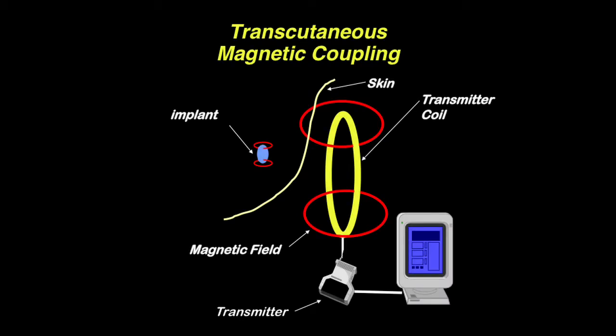We have an outside device that creates a large magnetic field by having a large current pass through it. This magnetic field easily penetrates the tissue, can be coupled to a smaller coil that's inside of the device, and in this way we can transfer energy to the device. Now what's convenient about this is then we can change the transfer of the energy in order to communicate with the device. So we can put a carrier, if you will, on top of the wave that is carrying the energy. We can use the same link to communicate from the device back outside the body. So with two simple coils, we can have a very effective power and communication range.